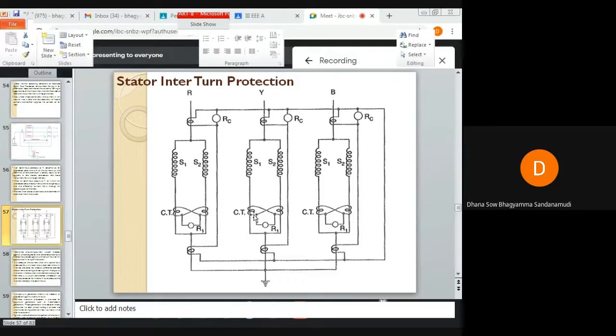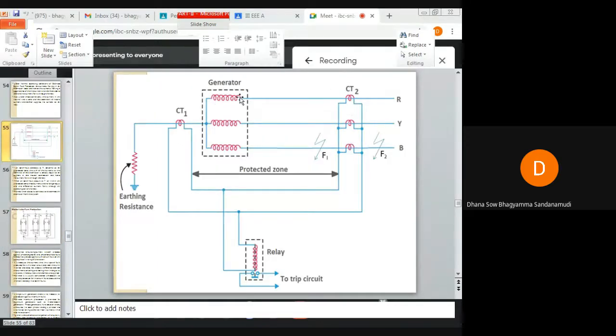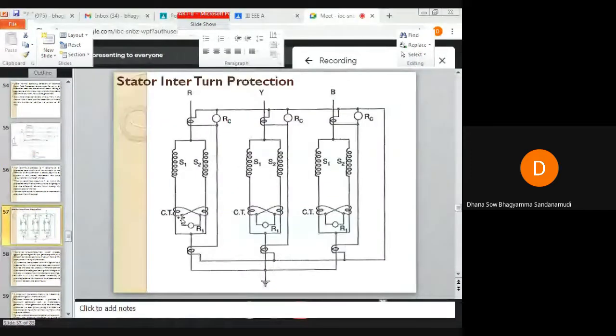But protection must be provided if the cost of the equipment is very high. If it is a very small equipment and more turns are not there, of course interturn protection is not required. If there is only one turn, then for one-turn generators like this, interturn fault protection is not at all required. But some generators, such as hydroelectric generators, will have multiple turns.